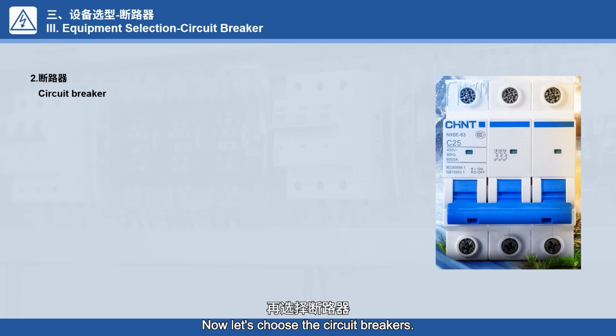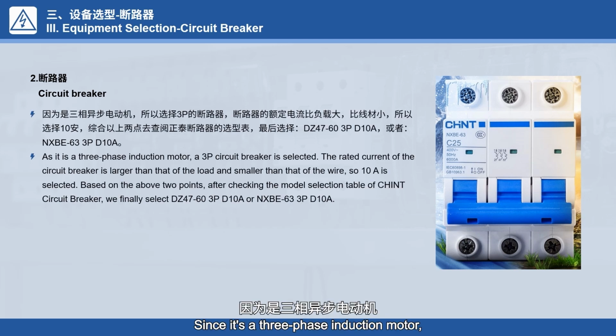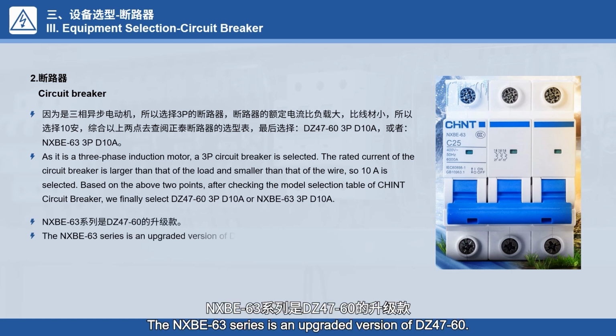Now let's choose the circuit breakers. Since it's a 3-phase induction motor, we choose a 3P circuit breaker. The rated current of the circuit breaker is larger than the load, but smaller than the wire size. So we choose 10 amperes. Considering the above 2 points, we consult Chint's circuit breaker selection table, and finally choose DZ47-60 3P D10 amperes, or NXBE-63 3P D10 amperes. The NXBE-63 series is an upgraded version of DZ47-60.